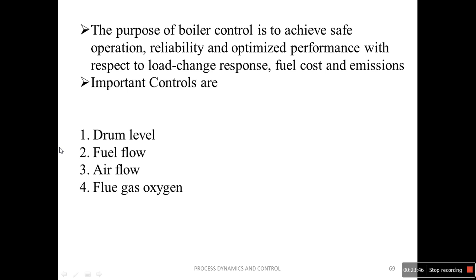Here, as an example of multivariable control, we are going to concentrate mainly on drum level control. Say this is a boiler drum, where the feed water enters, and from somewhere we get the fuel and air combination. By using the heat energy of that combustion, the feed water is converted into steam. The steam flows through this line, going to different process stations or different turbines depending upon the process. Here my aim is to control the level of this boiler drum. For that we have the level indicator.